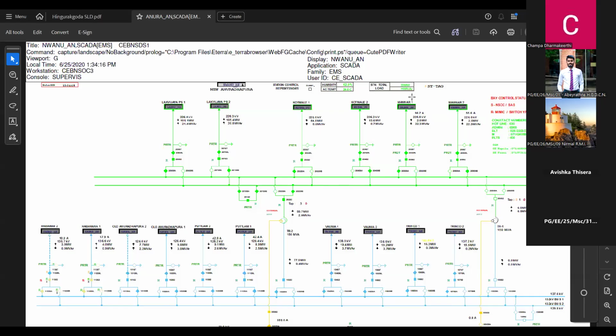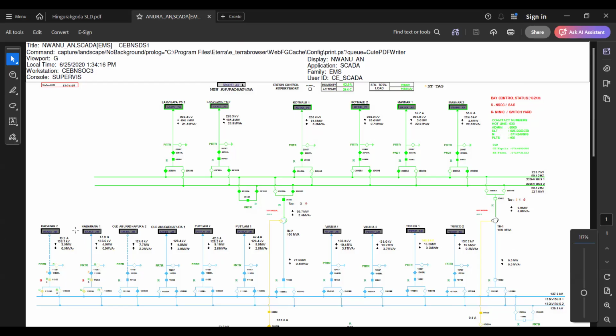You can see this is our new Anuradhapura grid substation, where we have feeders from Lakvijaya, that means the coal power plant, Kotmale, and Mana, and thereafter that green-colored network is the 220 network, and it is stepped down to the 132 network here from these two transformers. Those are 150 MVA transformers. There are two, and then 132 feeders go out to Habarana, Puttalam area, Vavuniya and Trinco, sending power to these areas. That means the upper part of the country is served by these feeders.